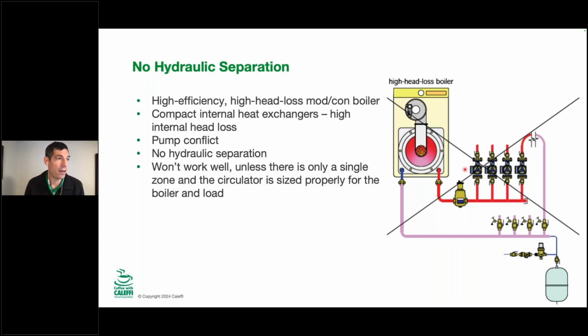Then we came back with these ModCon boilers, which are great for a million different reasons, but have a very much smaller capacity of water inside of them. So they aren't as flexible to high flow rates and low flow rates. If the flow rate's too low and you start to overheat, they have lots of safeties built in that are going to say, hold on, we need to wait a second. We're going to get too hot too fast and shut off.